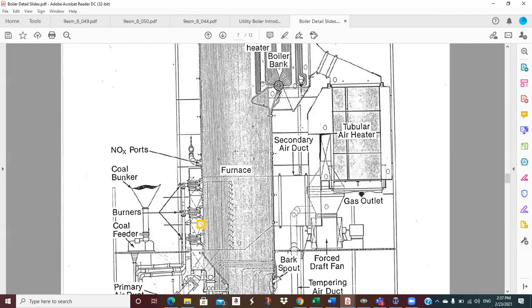So if we can stage that combustion, you know, partially burn it by the main burner, and then keep feeding air in downstream, we can keep it burning longer, but at a lower temperature. Then by staged combustion, we can minimize the amount of NOx that's generated. So, some of that going on.